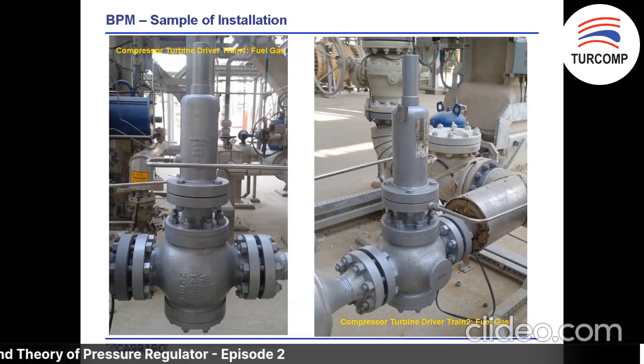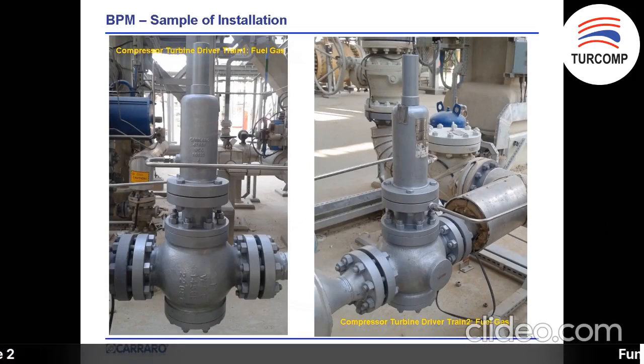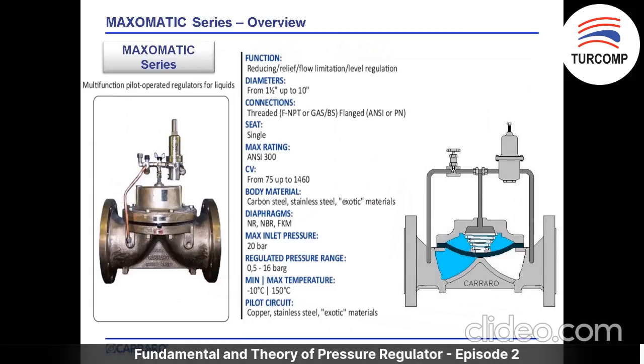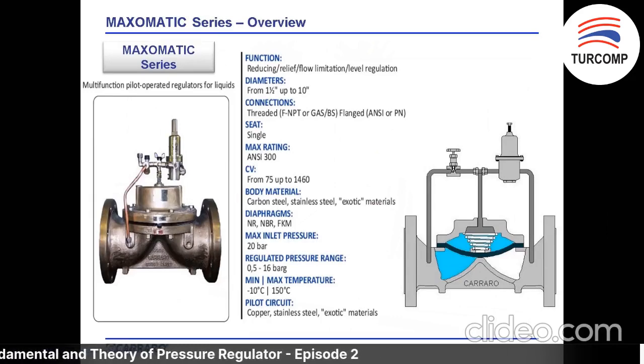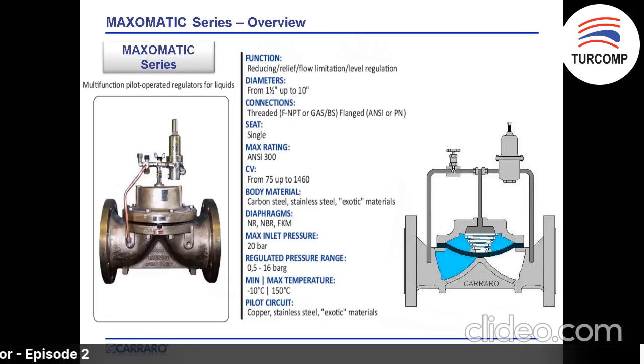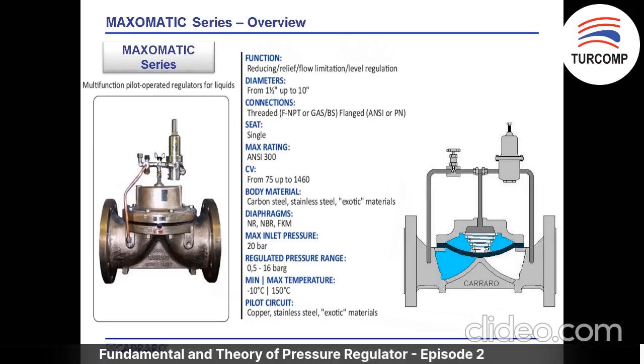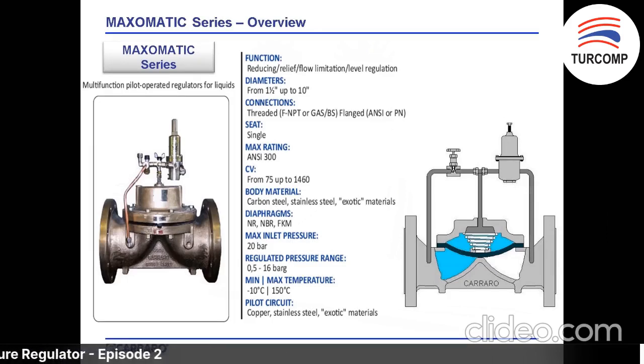Last but not least is the Maxomatic series — a particular pilot-operated valve. The body is always the same; by changing the pilot, you can change the function of the valve, which can be relief, reducing, level regulation, or flow limitation. It is suitable only for water applications — particularly firefighting systems, irrigation, water treatment, and special applications on shipyards. There are no moving mechanical parts or sliding guides, which ensures extended durability. It is very easy to maintain because, as with the UB series, the diaphragm can be removed with the valve installed on the line. Tightness is obtained between the resilient elastomeric surface of the diaphragm and the rigid metal seat of the body, ensuring tight sealing.